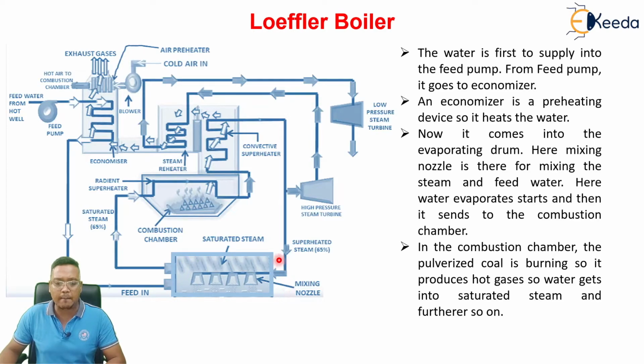In this mixing chamber, what will happen? The feed water is coming like this and the superheated steam will come like this. The feed water and superheated steam will mix and there is a formation of saturated steam. Then this saturated steam will go into the radiant superheater. And this is the combustion chamber. The radiant superheater is present in the combustion chamber.